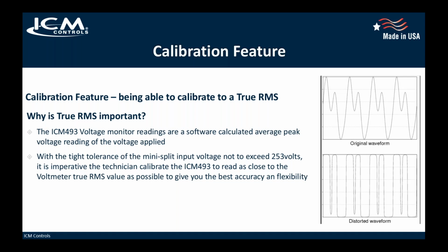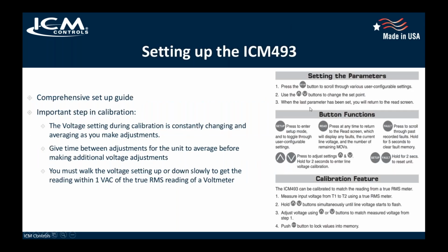With these tight tolerances of the mini splits, not to exceed 253 volts, it's very important that when you install a 493, you do calibrate it to read that value so you get the maximum benefit out of the control. Because like I said, you might be very near that 253 deadline. You might be only 7 volts away from it. So you want to make sure that your meter is reading within that setting.